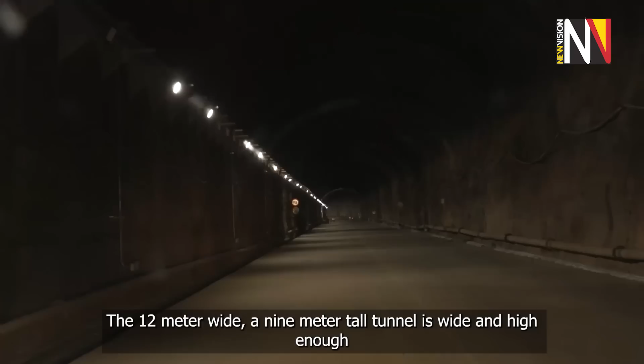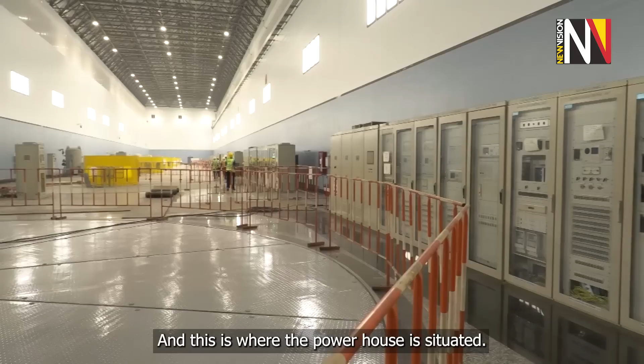Right now we are 100 meters underground from the surface, and this is where the powerhouse is situated. Because the configuration is an underground power plant, the powerhouse itself is underground. This was in a bid to increase the head so we could get a higher installed capacity from the same location, using the same storage or volume of water, but with an increased head, because it was initially conceptualized as a 200 megawatt plant.